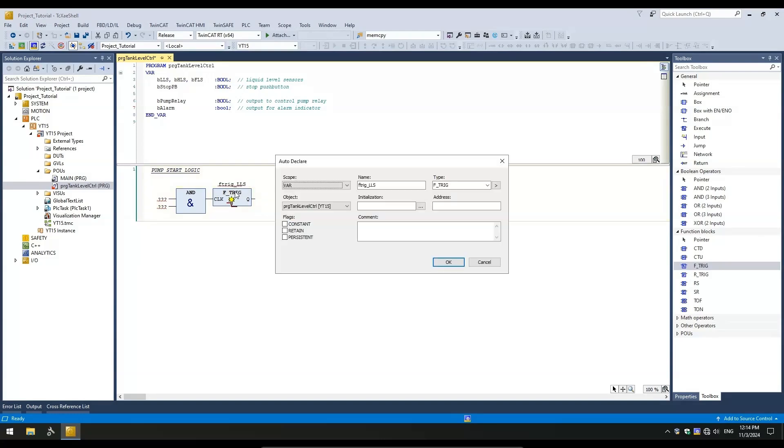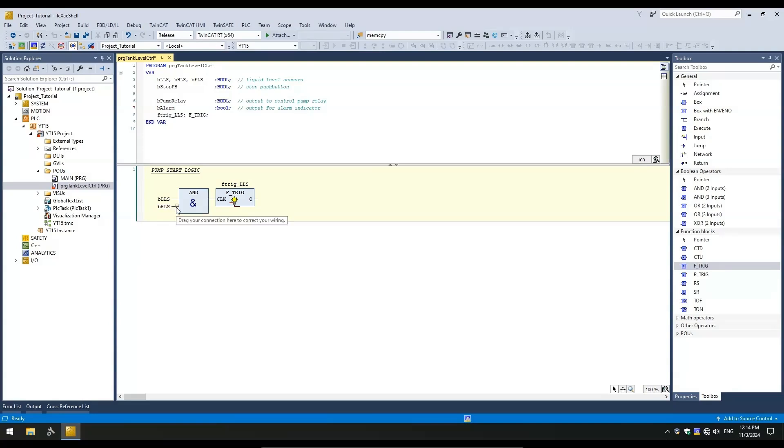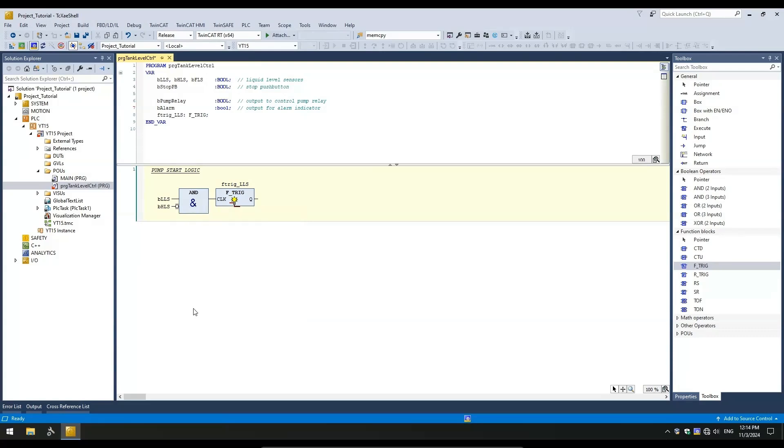Let's call it Ftrig LLS. In the AutoDeclare pop-up box, click OK to accept. Let's assign the variables to the inputs of the AND block. Since we want to invert the input condition for HLS, simply click on the input and right-click and select the negation option. You will see a small circle appear on that input, which indicates it is a normally closed input. So, a false on HLS will satisfy that input.